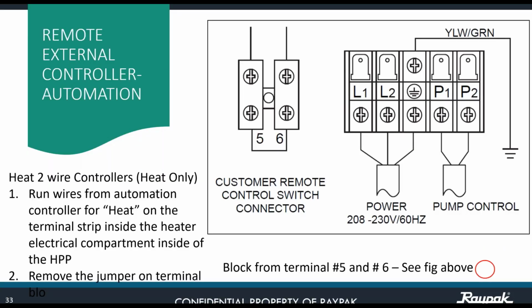Okay, so we need to run wires from the automation controller for heat to the terminal strip inside of the heater electrical compartment, inside of the heat pump. It's going to be exactly where numbers 5 and 6 are. In 5 and 6, you're going to find, guys, a jumper between those two lines. Remove the jumper and hook up the wires that you're bringing from the automation system. You don't need to do any programming. All you need to do is set the temperature on pool or spa to the maximum temperature, 104.